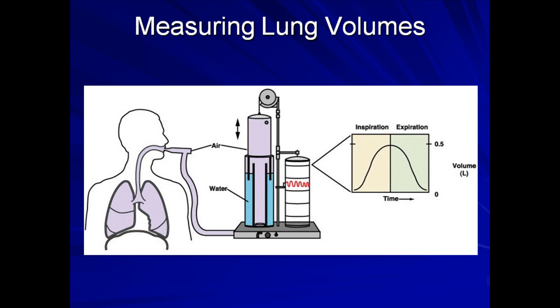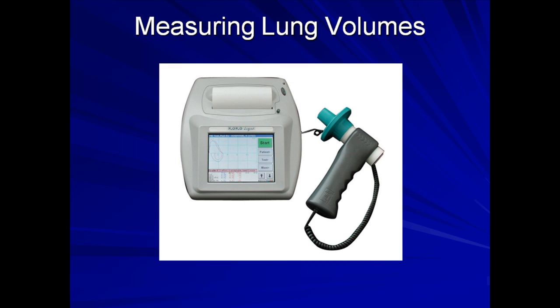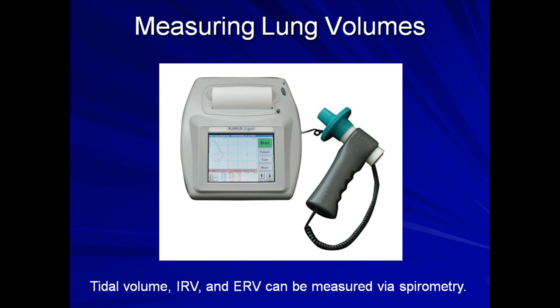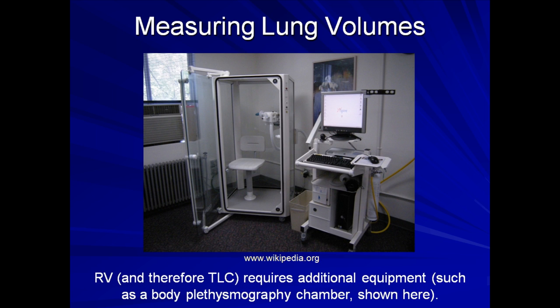Here is a more basic schematic of the principle on which Hutchinson's device worked — an example of a volumetric spirometer using a water bell to displace a recording device. Today, tanks of water and pulley systems have been replaced with circuits and a variety of techniques to measure air flow integrated over time. Standard spirometry is able to measure tidal volume, inspiratory reserve volume, and expiratory reserve volume, but not residual volume. Measuring residual volume, and thus total lung capacity, requires additional equipment such as a body plethysmography chamber. Due to the obvious practical challenges in employing such devices in the ICU, measurement of residual volume is essentially never done in mechanically ventilated patients.